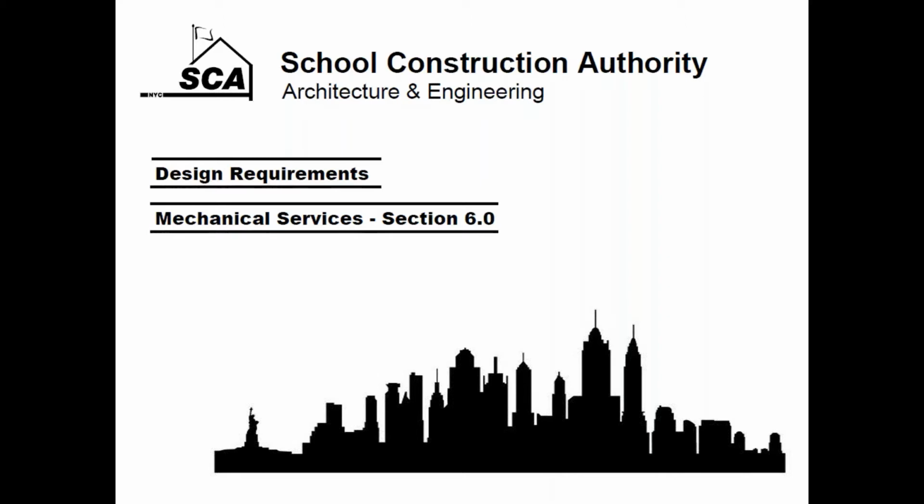Keep in mind, though, the code does not touch on A, B, C, D. The code just says ASSE or PDI. ASSE, when you dive into that standard, that's when it mentions the 4 types. But the actual plumbing codes do not go into that much detail. You just have to be ASSE. And if you're ASSE, it doesn't matter what type you are, as long as you meet that standard. Good question.